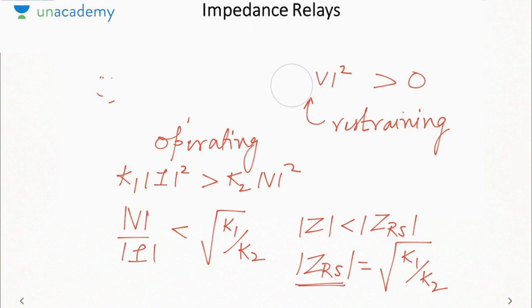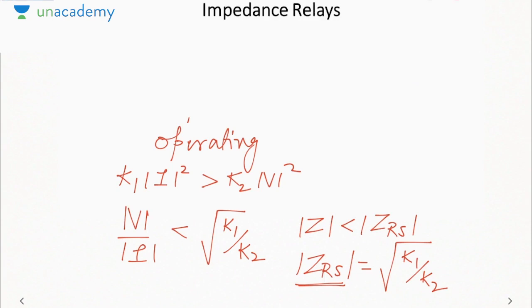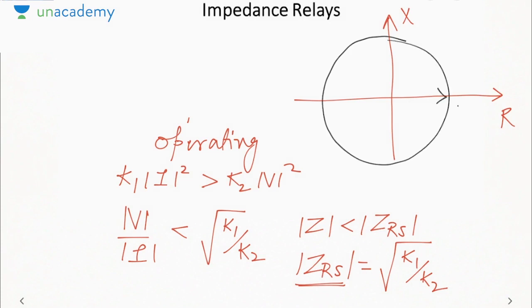Now if we wish to draw the characteristic of this relay on the Z plane, Z means resistance and reactance plane, Rx plane. Now the boundary condition will be mod Z is equal to mod ZRS. Now whenever mod Z is equal to constant, it represents a circle centered at origin. So it will be like this. The radius of this circle will be mod ZRS. Now the region of operation of a relay is when mod Z is less than mod ZRS, that is the interior of the circle. So here the relay will trip and outside this the relay will block. Okay. So remember, this is the characteristic of the impedance relay.